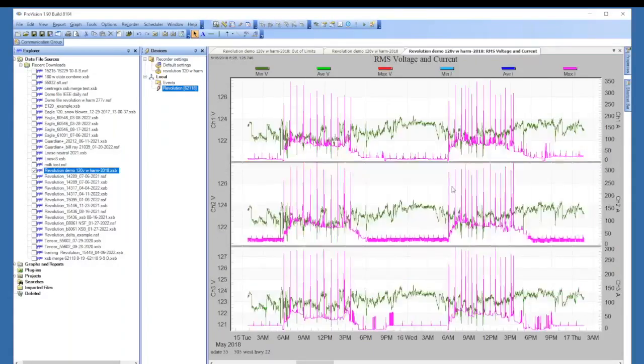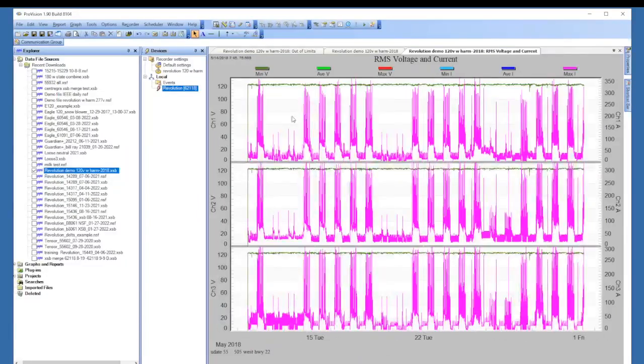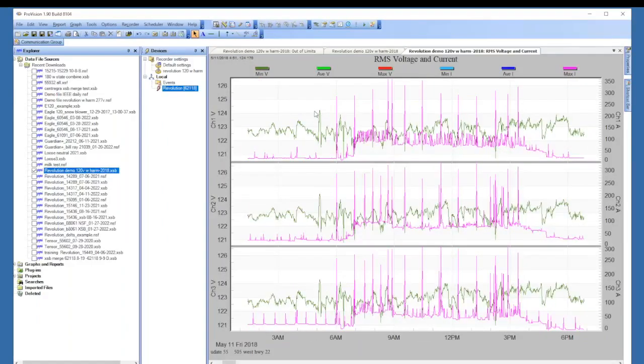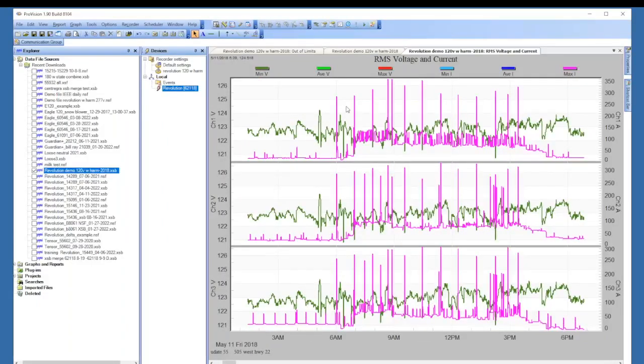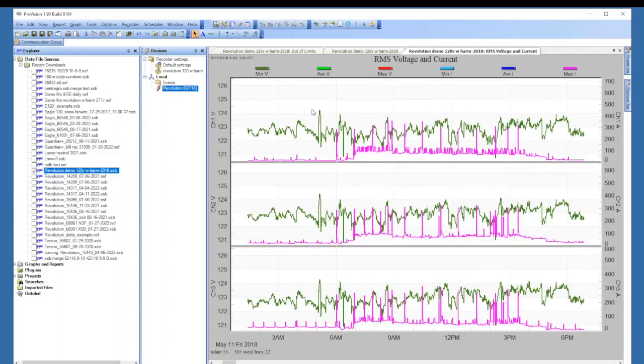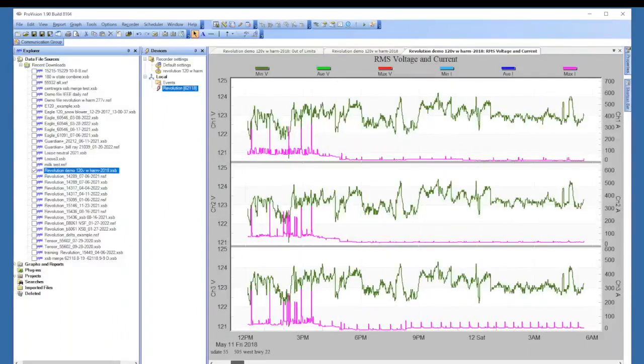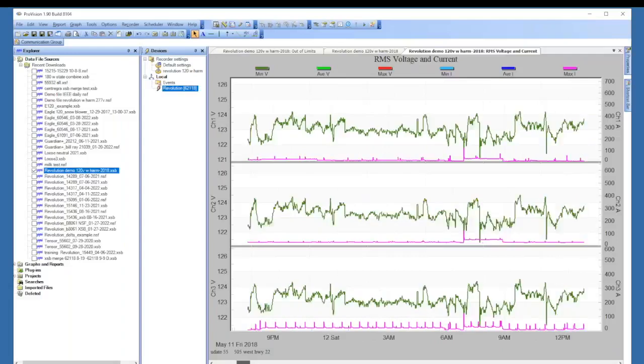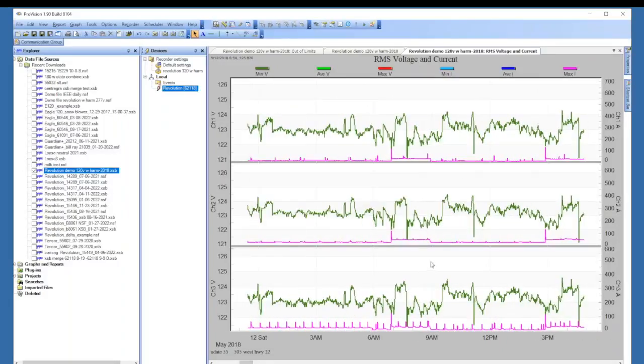And I'll click OK. And so what we have is the minimum voltage in the green and the maximum current in kind of the pinkish. If we hit our Z key now, we can see that it goes all the way out. And we'll even drop that a little bit. But anything that doesn't match up with the inrush would mean that any of the voltage fluctuations are coming from further up the line. So here you can see we've got a couple of small drops here.